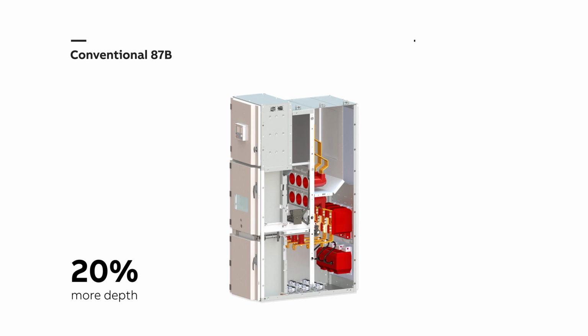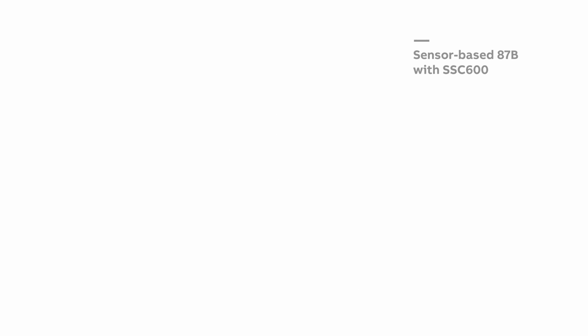For comparison, here you can see a panel with current and voltage sensors only. There is no need to have any conventional CTs. The current sensor is located here, or you can also have two sets of current sensors. The voltage sensor is this small part and it is made of epoxy resin. This means that there is also a large reduction of the weight and footprint of the switchgear panel.